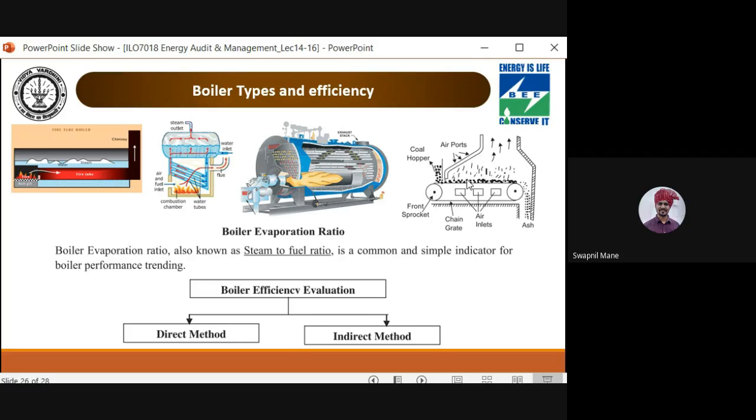Okay, as we see, the firing is uniform for the chain grate boiler. For the pulverized fuel boiler, we have a continuous fine powder which is fired from all sides, and in between we have a big lump of heat which passes. And if you want to measure the temperature of such a boiler, then we see that around 1300 to 1700 is the temperature, depending upon the grade of coal that you are using. So here the incomplete combustion is totally eliminated, but still we find that if the micron size is not properly maintained, then you have incomplete combustion at the end.